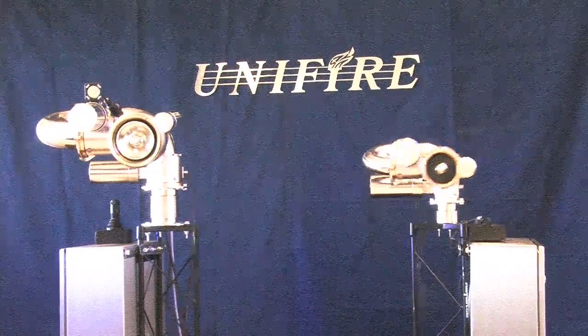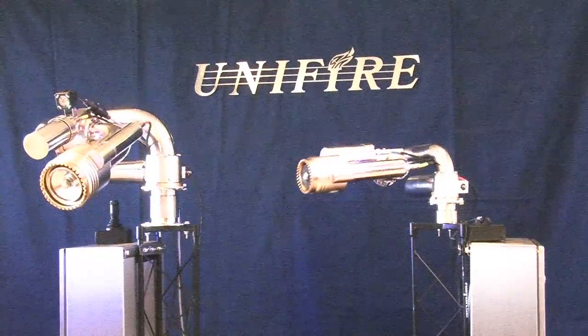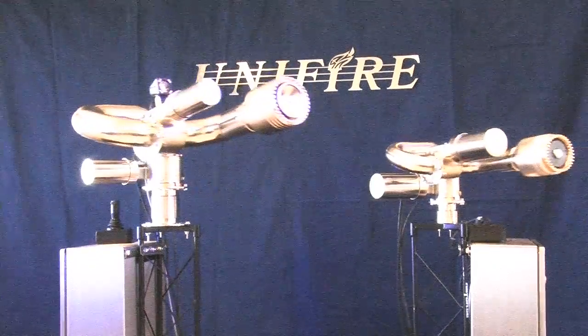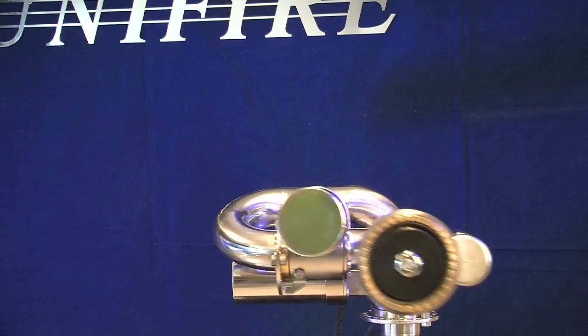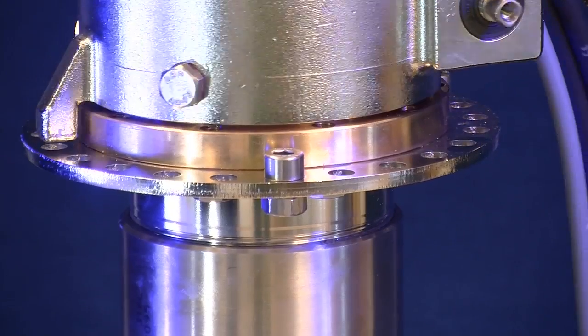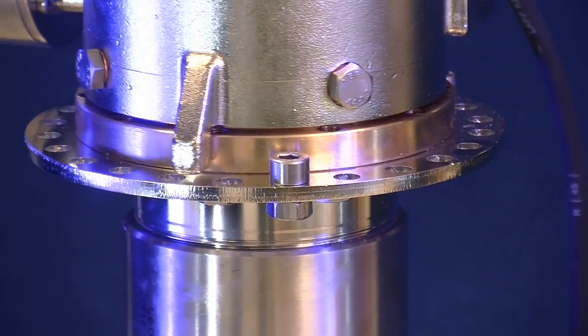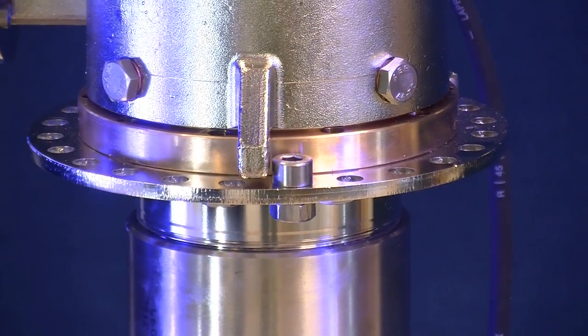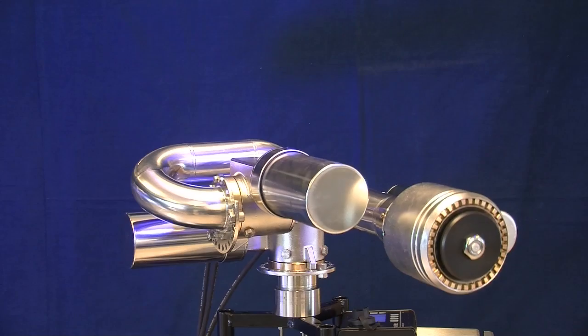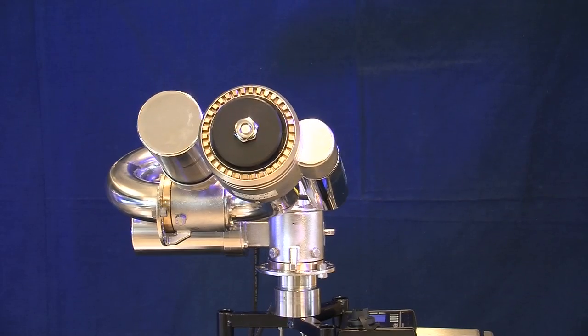Unifire Force Monitors are capable of rotating 360 degrees horizontally and 180 degrees vertically. The water cannons feature limit bolts to allow you to mechanically set the limits of operation. Once the limit bolts have been placed and the cannon has been calibrated, the cannon memorizes its limits and does not hit the limit bolts in the future, saving wear and tear on the motors and gears.